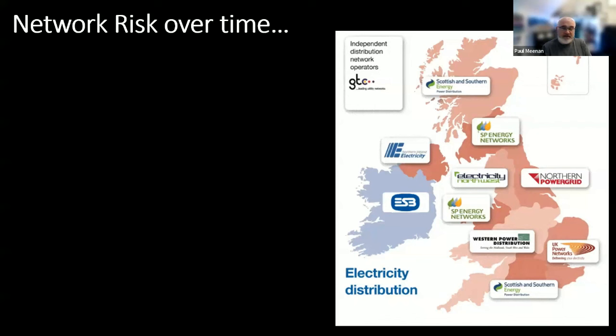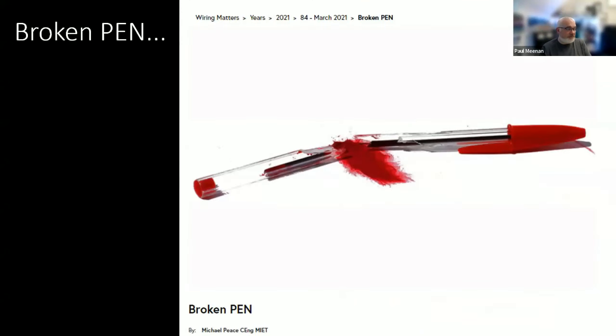Now, if you think about that, in the 1970s, the cabling in the streets was 50 years old. So they introduced new cabling, new earthing systems. And we now have a hybrid of the new and old. But before we get into that, there's an IET article, just Google broken PEN. Very, very good article from Michael Peace, who discusses the subject very succinctly. And that is the hazard. That is the hidden mystery that we're now on a journey. So everybody in the UK is on a journey looking at broken PENs, protective earth neutral conductors, and the hazards related to it. And what we'll do is we'll go into that now.